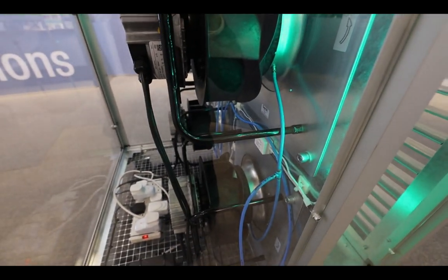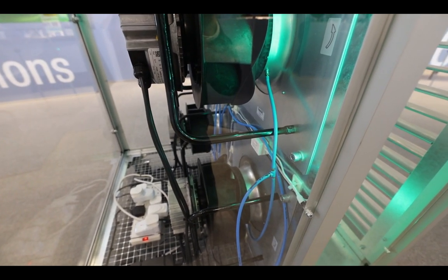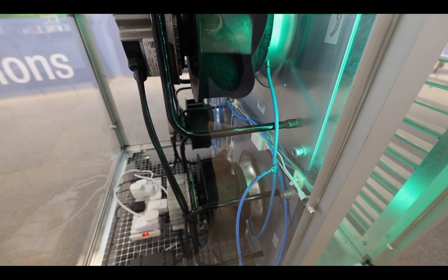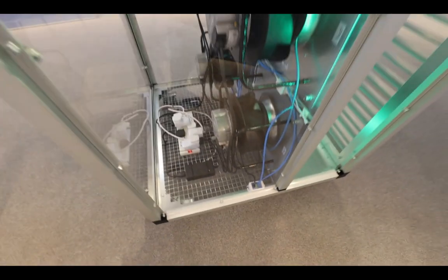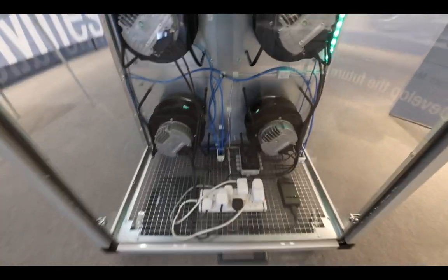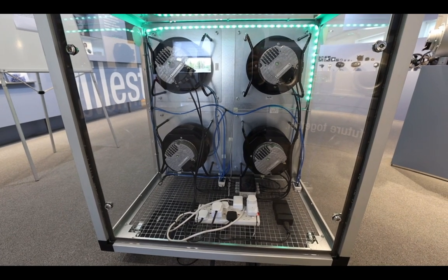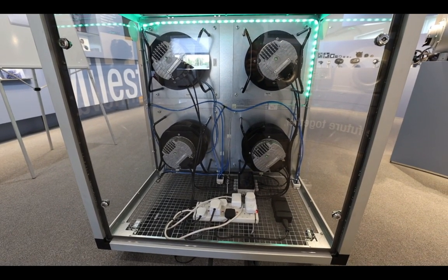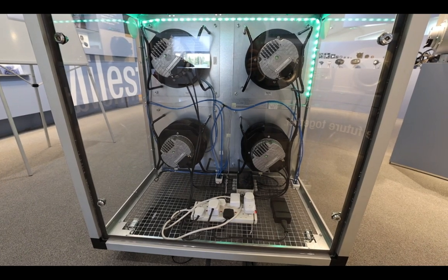The fans have also been equipped with a pressure tapping on the inlet ring with tubing installed and connected to single or multiple differential pressure transducers. Remote control switches have been installed to simulate the response of the control system in the event of a fan or a sensor failure.